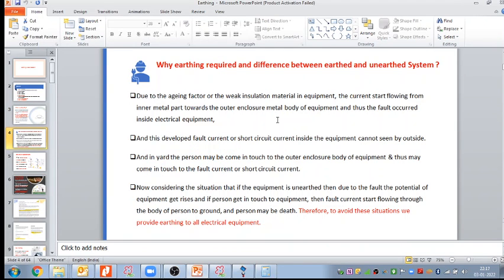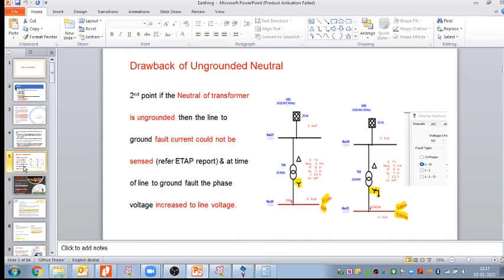Earthing and the difference: why earthing is required, and the difference between an earthed and an unearthed system. This we have also discussed. Then the drawback of an ungrounded system, the second point. If we do not do the grounding, then we cannot sense it: the neutral of the transformer is ungrounded, so the line to ground fault could not be sensed. That is the drawback of the ungrounded system.